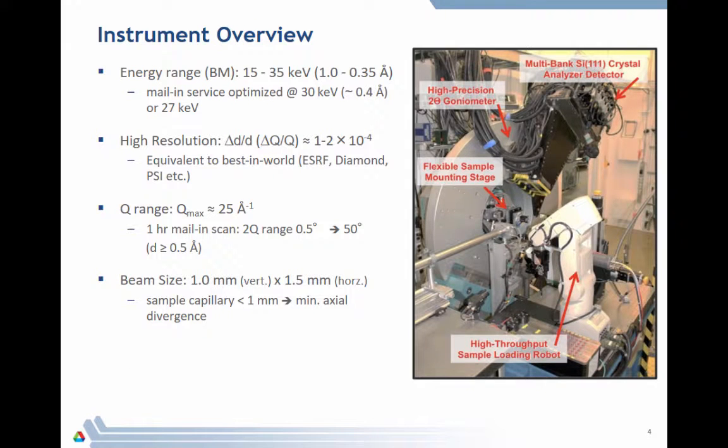So at 11-BM, we normally work at 30 keV. We found that's the good balance between penetration and flux for most samples. We can change from 15 to 35 keV. We are a high-resolution instrument. Our ΔD/D is somewhere between, it used to be 2×10⁻⁴, now somewhere between 1 and 2, which puts us equivalent to the best in the world, if not the best in the world.